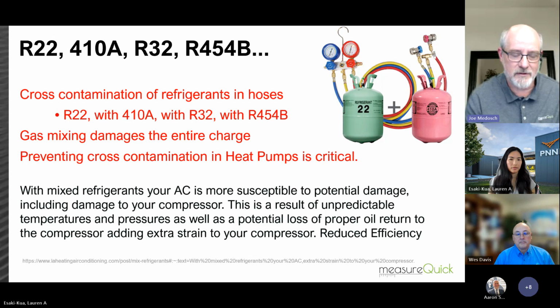In theory, if you stick with gauges, you need a separate gauge for each refrigerant so you don't end up with cross-contamination. That's not common in the industry since people aren't willing to spend that kind of money. You're better off putting money into a smart probe that won't increase contamination. I won't deny that hooking up any gauge, smart probe or not, causes a little bit of release, but it's a whole lot less than leaving refrigerant in a 5-foot hose.